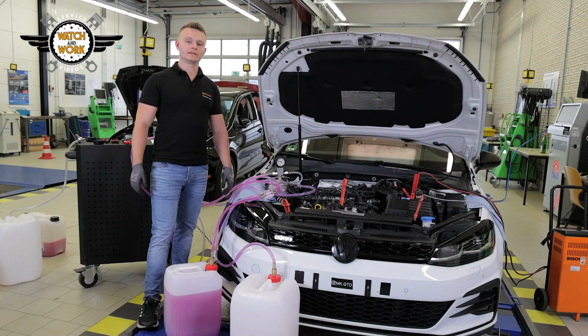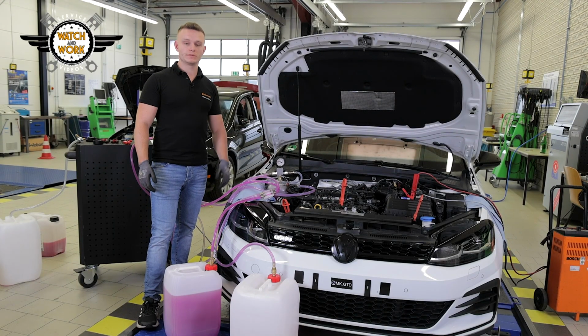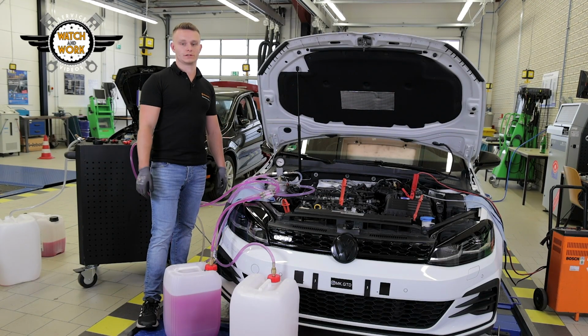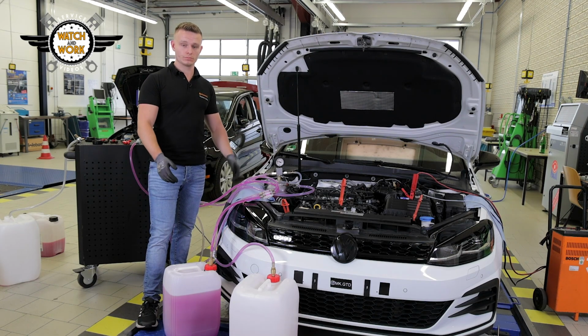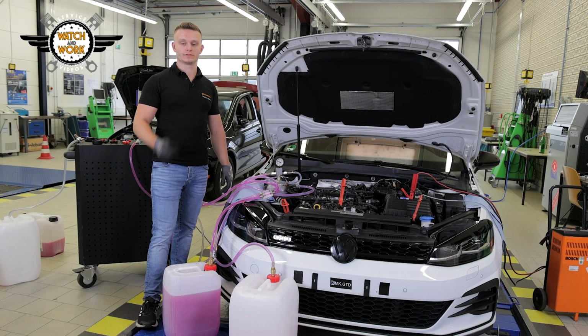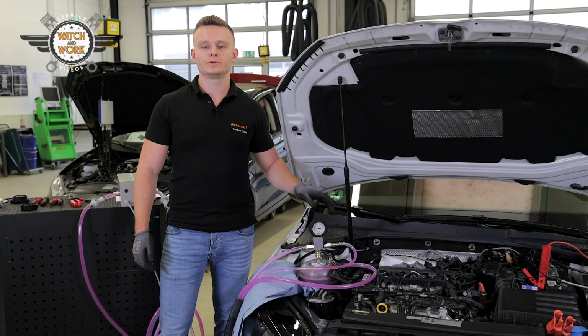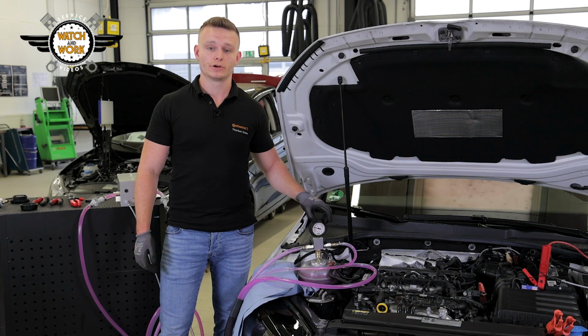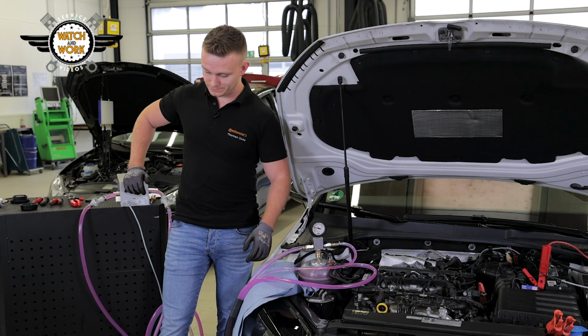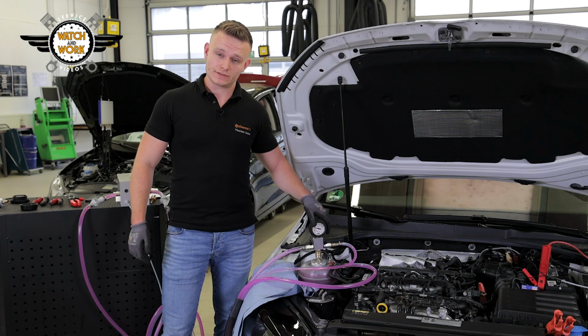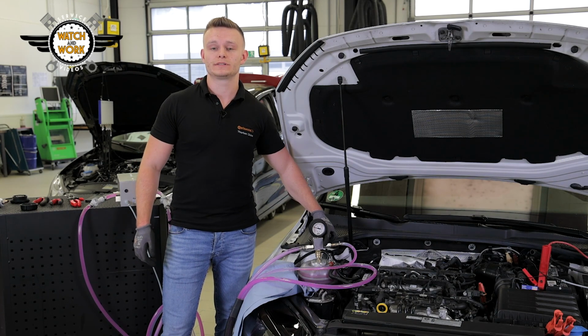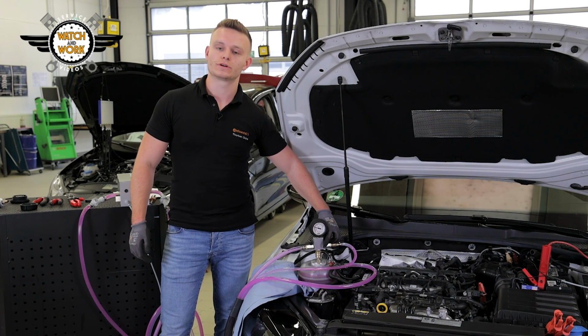We then carry out each of the separate flushing processes using coolant, just as we did with distilled water. Reposition the pinch-off pliers in accordance with your OEM instructions and flush the individual circuits twice. Once you have flushed all 4 cooling circuits with coolant, you can switch the pump off. There may be some residual pressure in the system. Just open stopcock B to allow the pressure to drop.